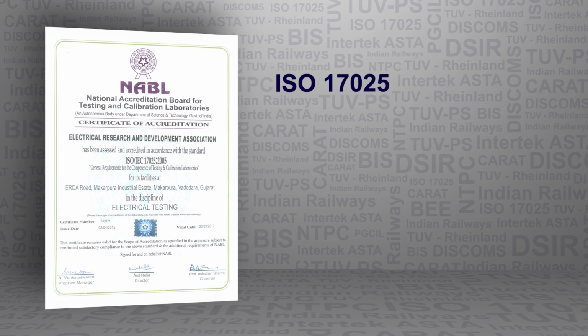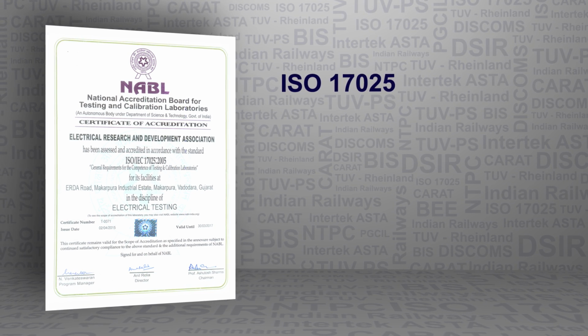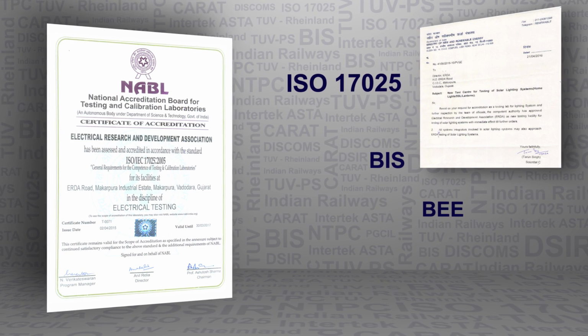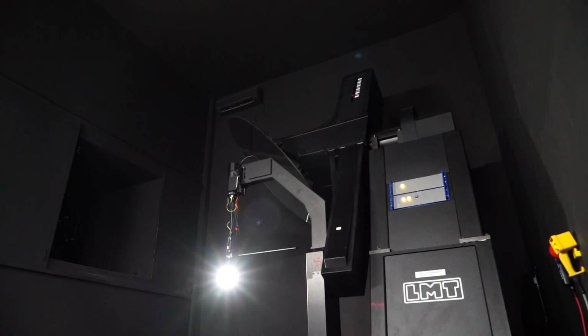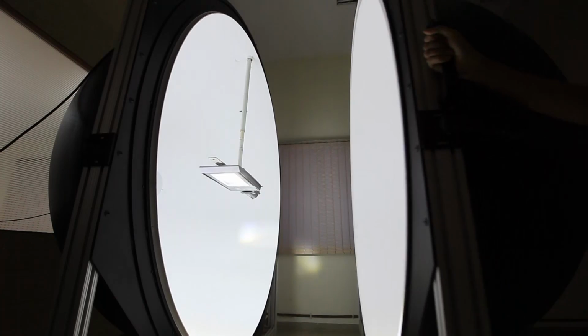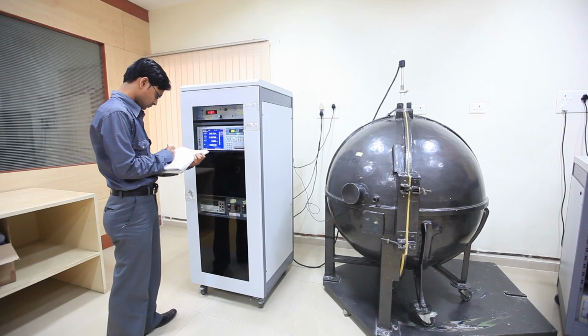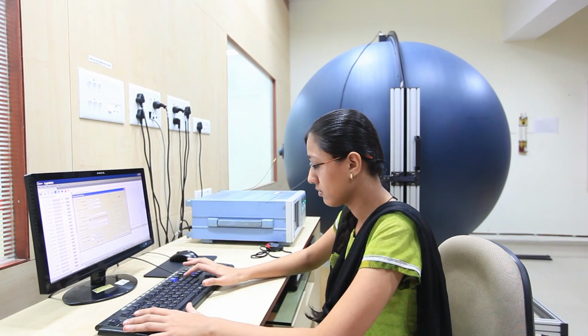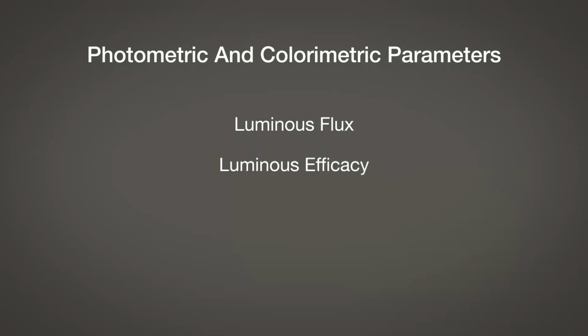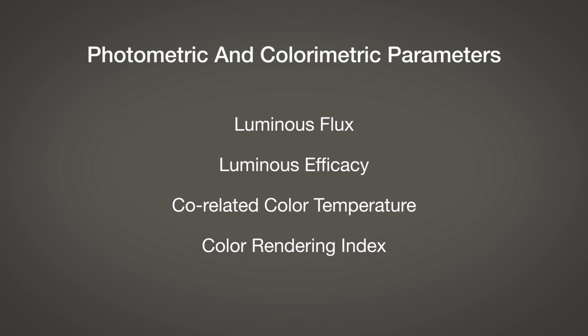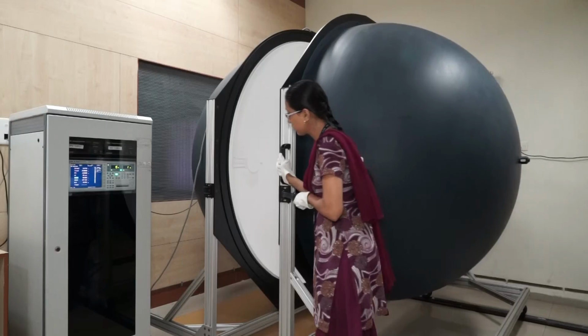This facility is accredited by NABL as per ISO 17025-2005, BIS and BEE. The laboratory is equipped with specialized equipment like integrating sphere with spectral flux measurement system. This system measures photometric and colorimetric parameters like luminous flux, luminous efficacy, correlated color temperature, color rendering index, and chromaticity coordinates. We also undertake optical calibration of all kinds of lamps.